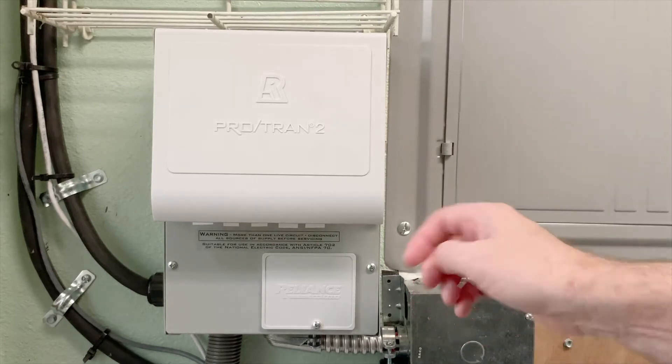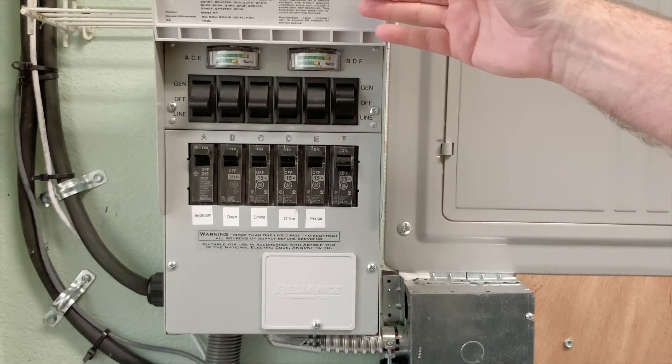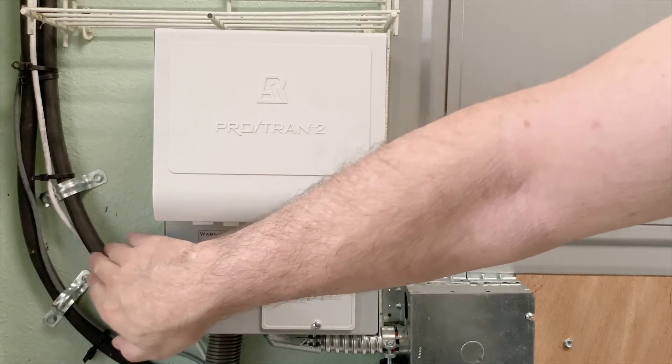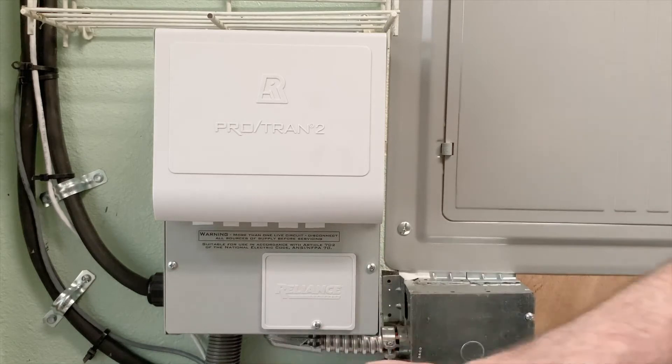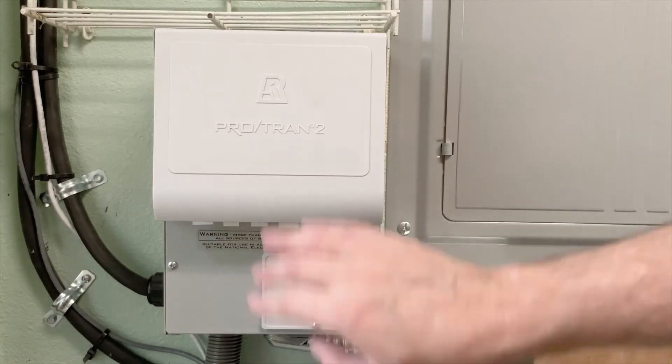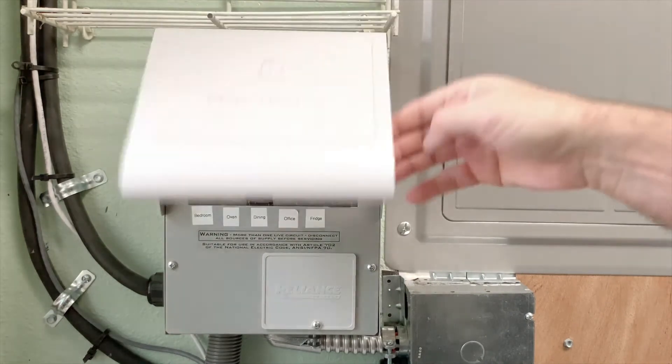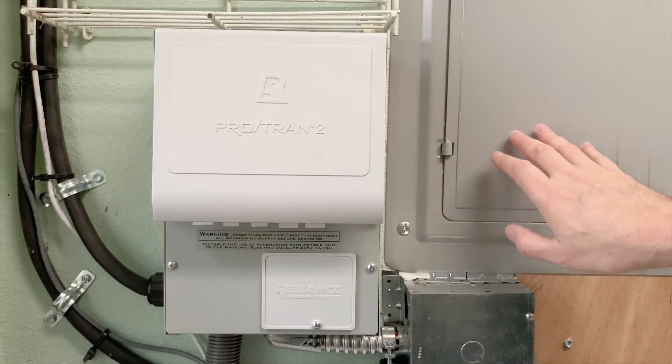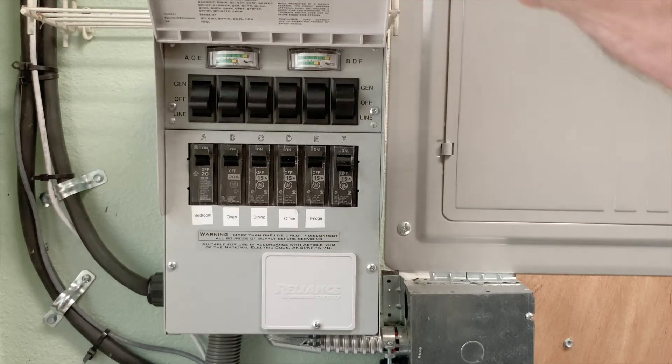This is the secret right here. This is the Reliance Pro-Tran 2. It's a manual transfer switch made to be used with generators, but it works perfectly fine with solar-powered inverters. This is the power coming from the inverter going inside, and I'll show you in a minute how this is all wired on the inside. Then after it goes through the breakers and switches, it will go through this conduit, a bunch of cables that come with it, and feed into your breaker panel, and I'll show you how all that is wired in a minute. But first, we'll talk about how it works.